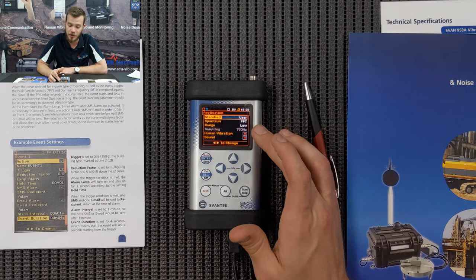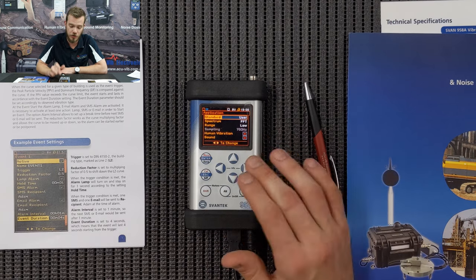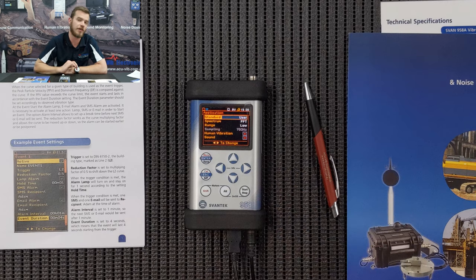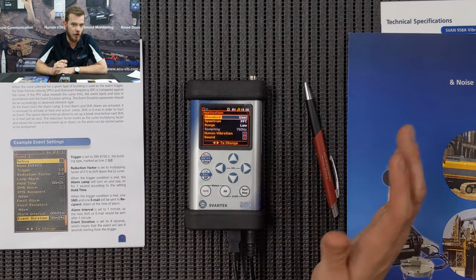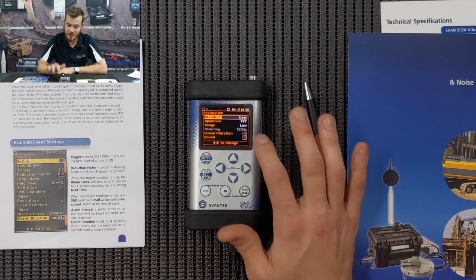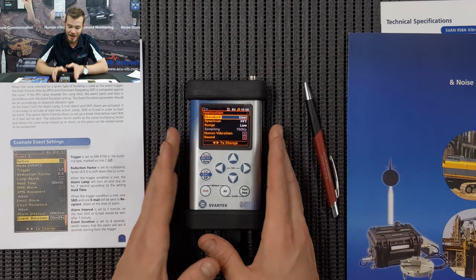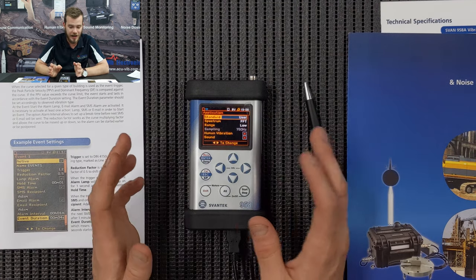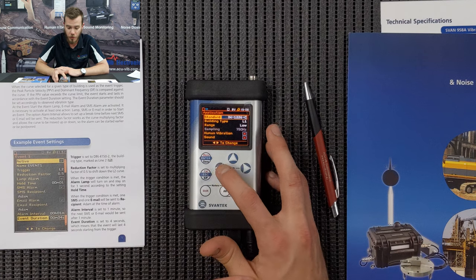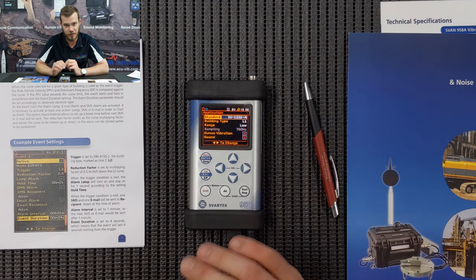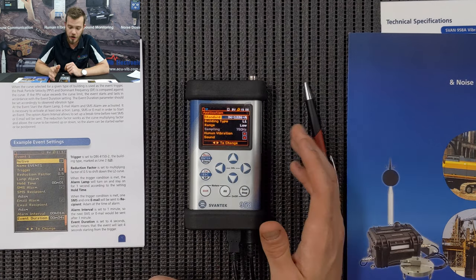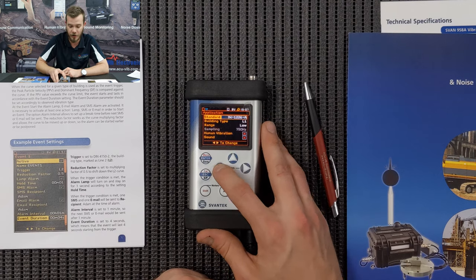Now, the last one is also a user-defined standard. So you can create your own criterion curves based on whatever requirements you need to monitor. This is where you can do it. For today's purposes, I'm going to run you through the DIN standard because that's for a lot of requirements in Australia. I know in New South Wales especially, they're being urged to monitor vibration in accordance to the DIN.